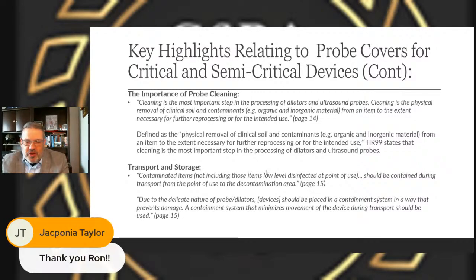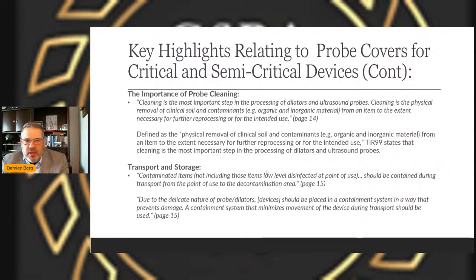And then transport and storage. Transport and storage is also a very important thing, because these devices are not typically stored in a sterile processing area or even in a sterile area like a sterile core. They're stored in rooms or offices or you name it, you've seen it all. As long as they're covered and protected from contamination or anything else like that, you're okay. Again, these are intended for intermediate or high-level disinfection, depending on the probe. But protect them, cover them, contain them so that people can't get to them. Environmental surfaces, sun, dust, all that stuff can't get to them, and they'll be fine to be used. It all talks about this in the document too, which is really nice. So hopefully that helps you a little bit on the probe document, TIR 99.